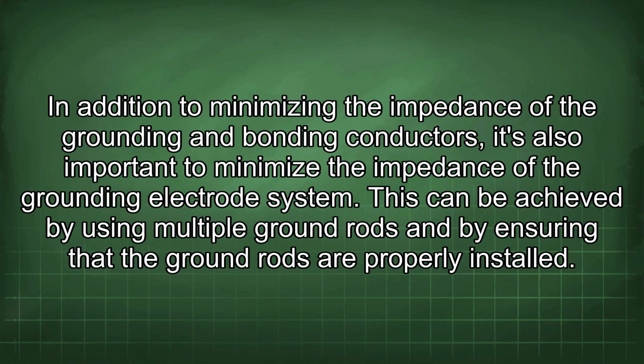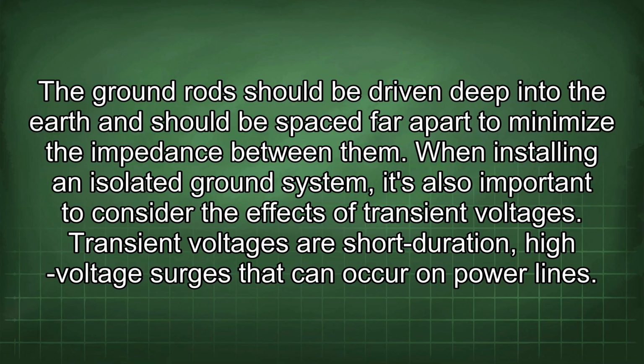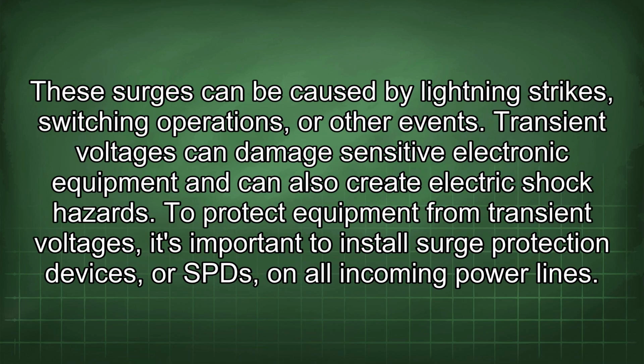In addition to minimizing the impedance of the grounding and bonding conductors, it's also important to minimize the impedance of the grounding electrode system. This can be achieved by using multiple ground rods and by ensuring that the ground rods are properly installed. The ground rod should be driven deep into the earth and should be spaced far apart to minimize the impedance between them. When installing an isolated ground system, it's also important to consider the effects of transient voltages. Transient voltages are short-duration, high-voltage surges that can occur on power lines. These surges can be caused by lightning strikes, switching operations, or other events. Transient voltages can damage sensitive electronic equipment and can also create electric shock hazards.